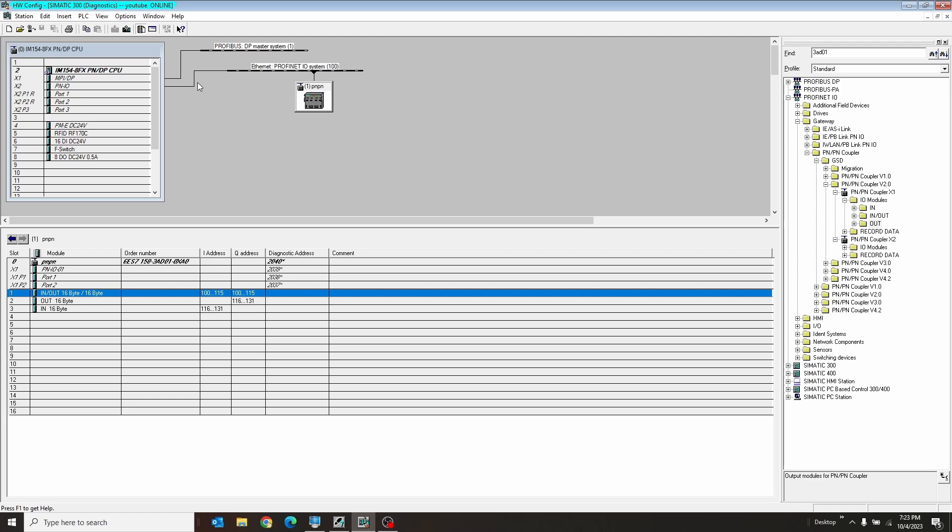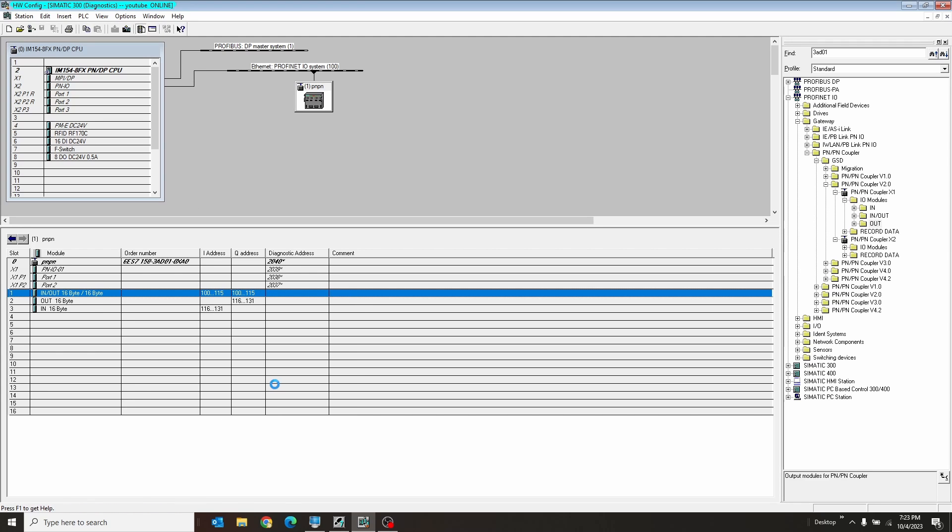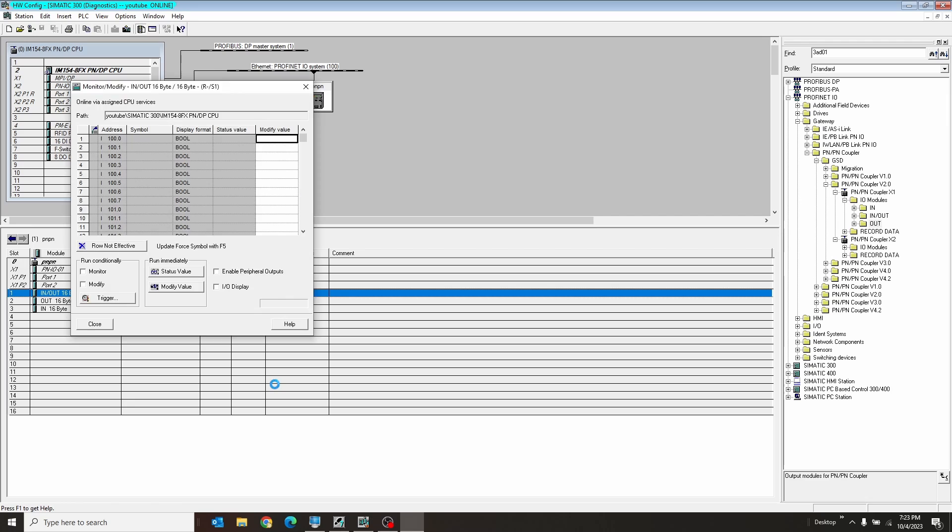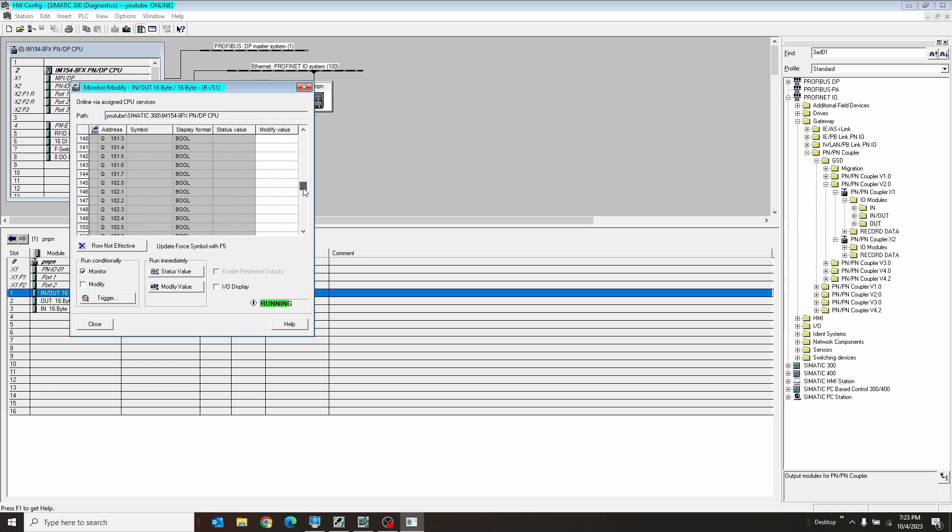Real quick, just to show this thing working, let's go ahead and right click on our in-out here. Let's go to modify and monitor. Hit monitor. These are all our inputs coming in. We want to skip all past this and go to our Qs. And let's just go to say our third Q. Hit one, enter. We'll hit modify. So that turns on the third bit of the outputs.